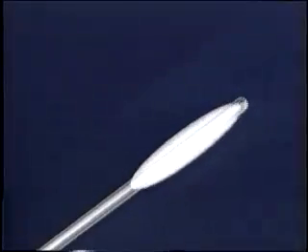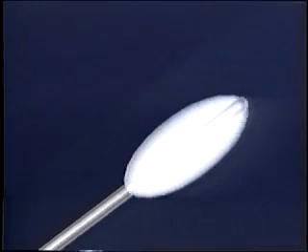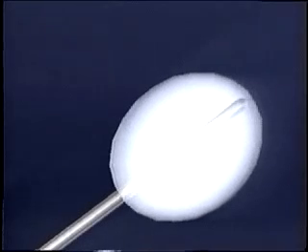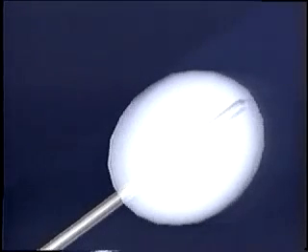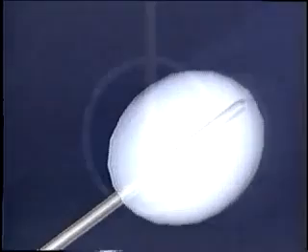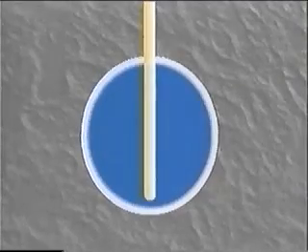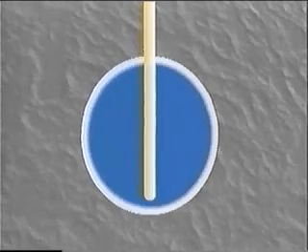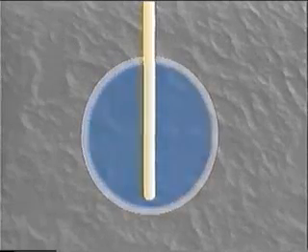In order to achieve the highest probability of cell destruction, a cryosurgical device must cause intracellular ice formation at a temperature which is sufficient to induce cell death. Clinical experience and physical constraints suggest that all cells will freeze internally near -50 degrees Celsius.